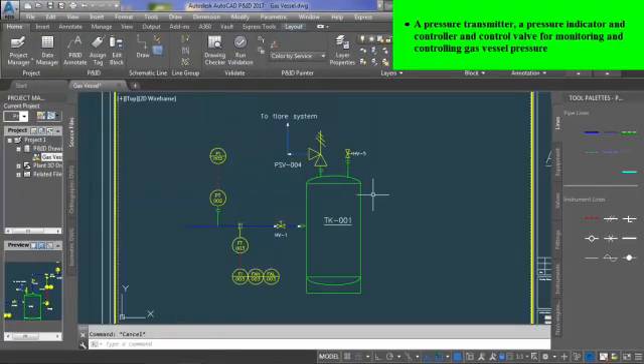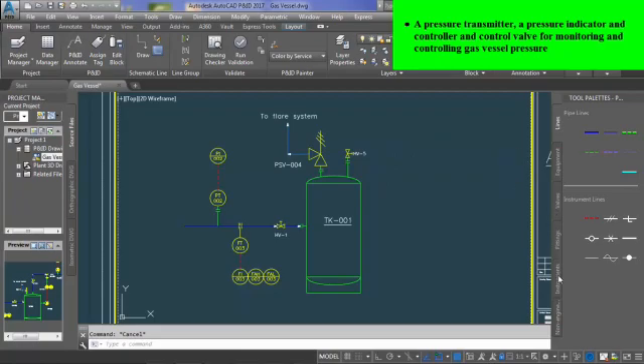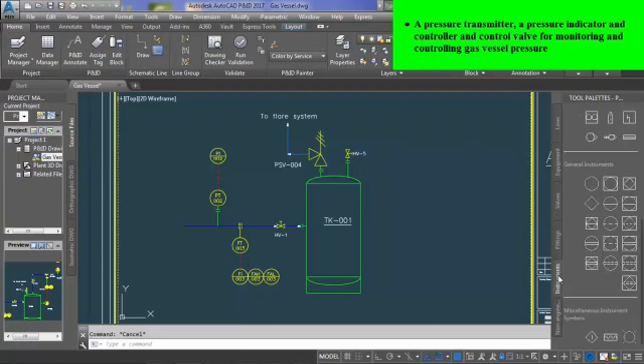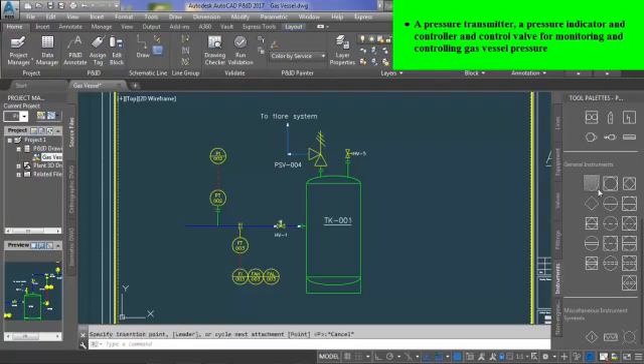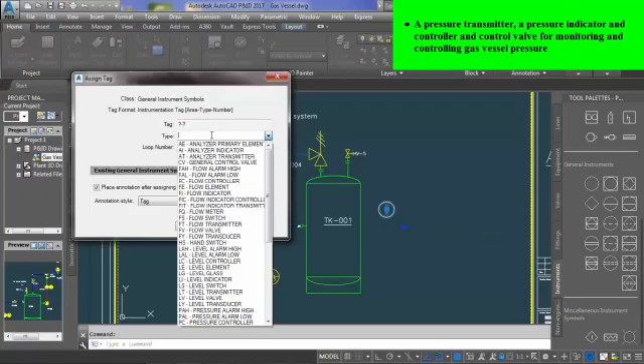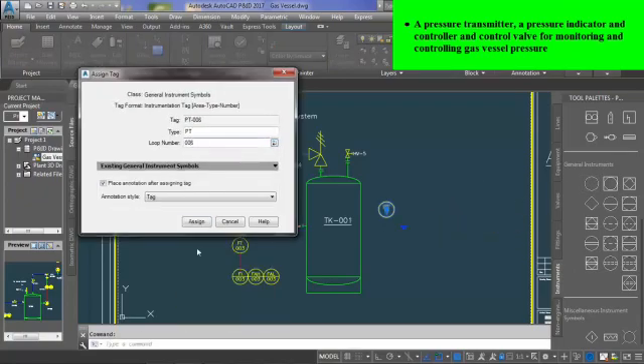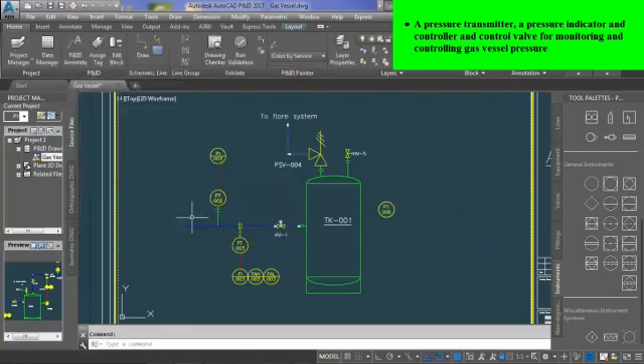Okay, now it's time to draw the control loop for controlling pressure of the tank. The first component is a pressure transmitter for measuring gas vessel pressure and sending the signal to pressure indicator and controller to indicate the measured pressure. At the same time, the pressure indicator controller will send a pneumatic signal depending on its set point to actuate the pressure control valve. Simply insert field discrete instrument and assign tag PT-6.